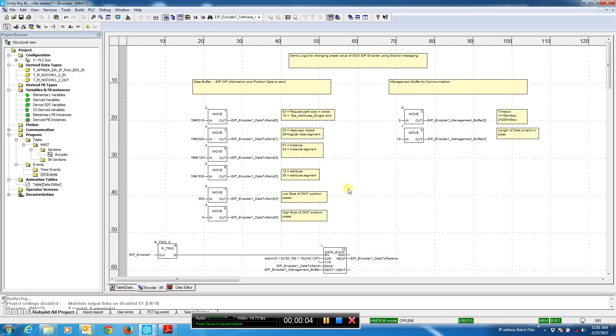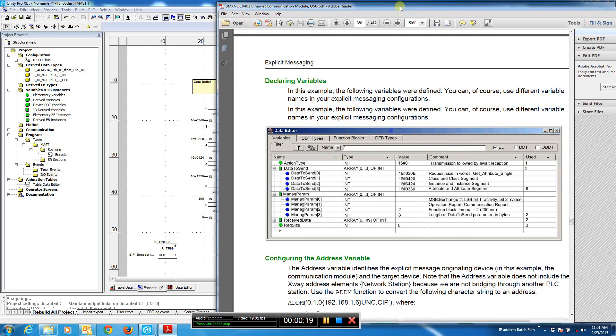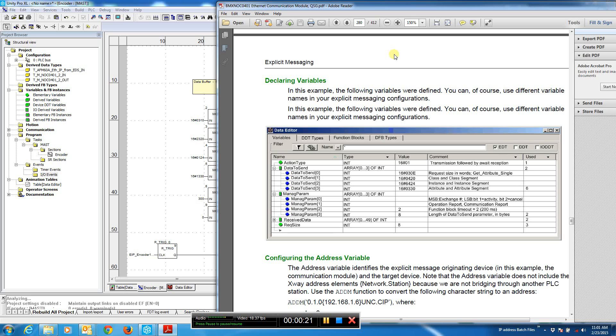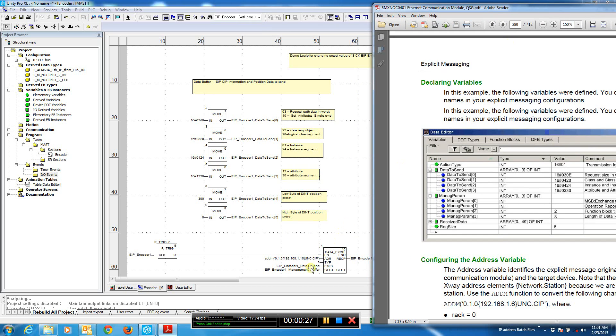In this video, we're going to set the actual position of a SICK Ethernet IP encoder talking to a Modicon M340. We're going to use explicit messaging using the set attribute single command mode. If we take a look at the actual manual on setting explicit messaging out of a BMX NOC module, we can see that we have to use a command called the data exchange command using an M340.